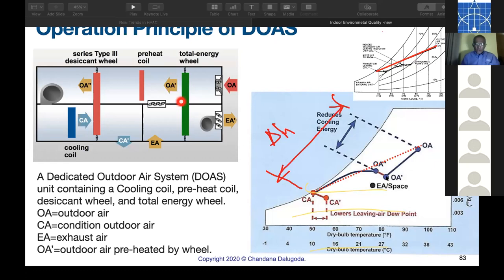We have a total energy thermal wheel. That is a thermal wheel, but we have energy thermal wheels that are slowly rotating. What it does, cold air or return air at 24, 25 degrees C cools the incoming air and also dehumidifies because it removes water vapor. So cooling and dehumidification, mind you, this is free. This is free, OA to OA dash is free. This is free.